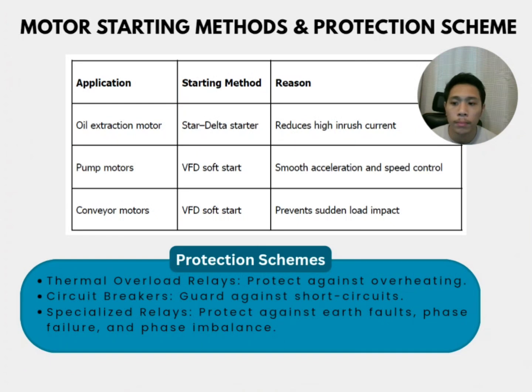These aren't just for starting, but it also allows us to precisely control the motor speed by adjusting the frequency. This soft-start capability prevents mechanical wear and ensures the system lasts longer. To ensure the facility stays operational, we must have layers of protection. The first one is thermal overload relays to stop the motor if it gets too hot. The second one is molded case circuit breakers for short circuit safety. And the third is phase failure relays, which are critical in remote areas to shut down the motor if one phase of the supply drops out. This keeps our equipment safe and our maintenance costs low.